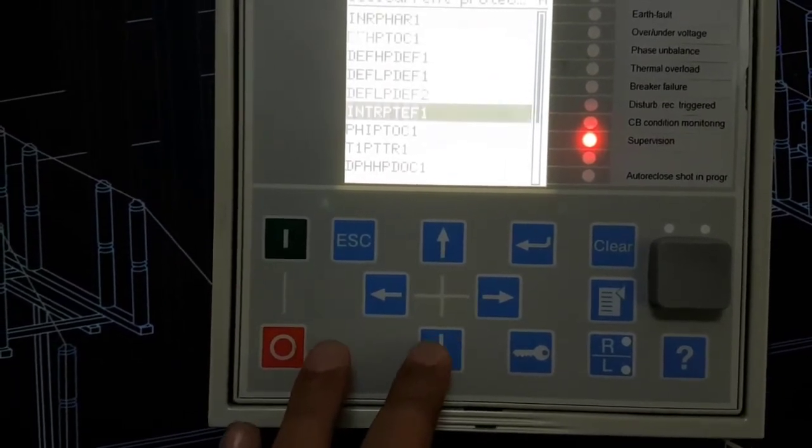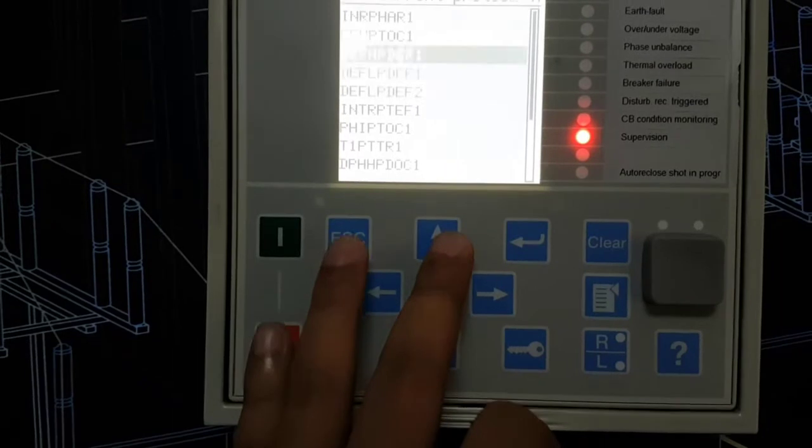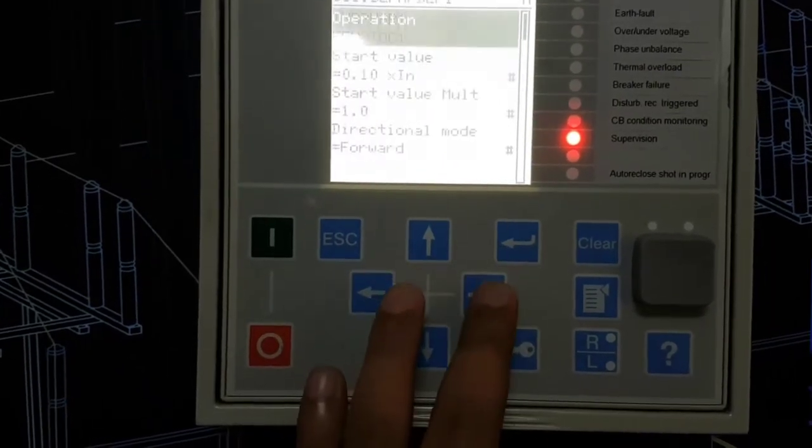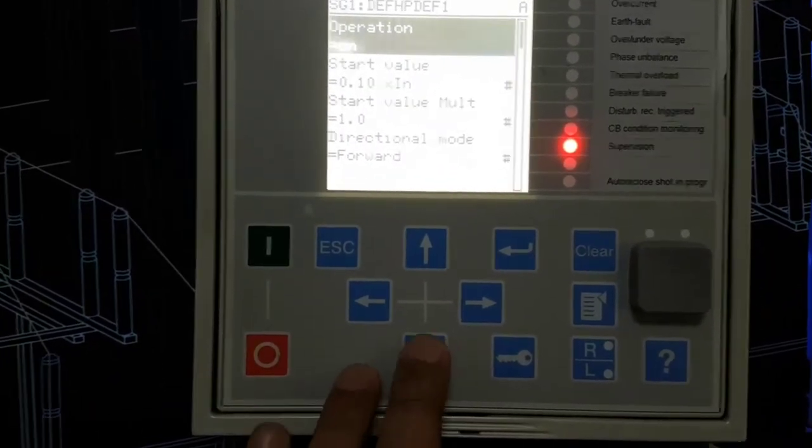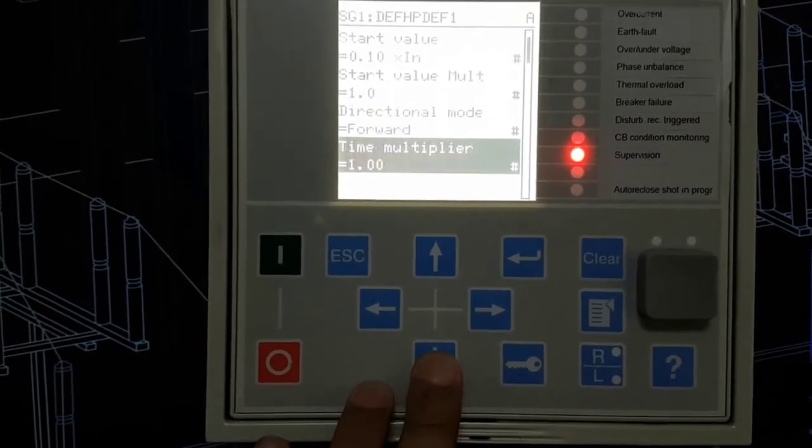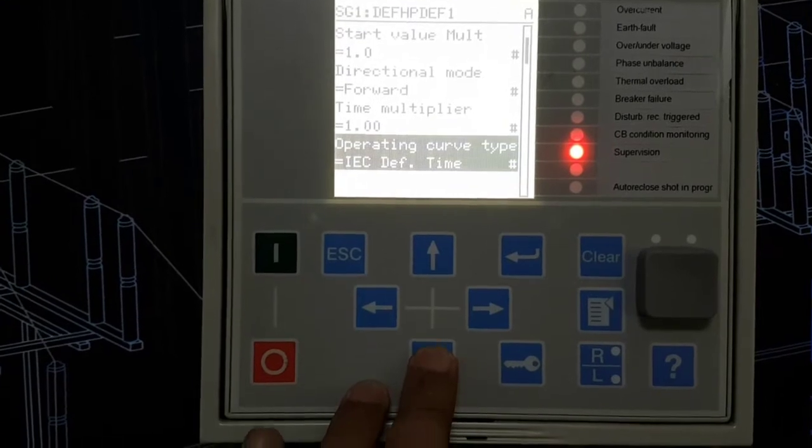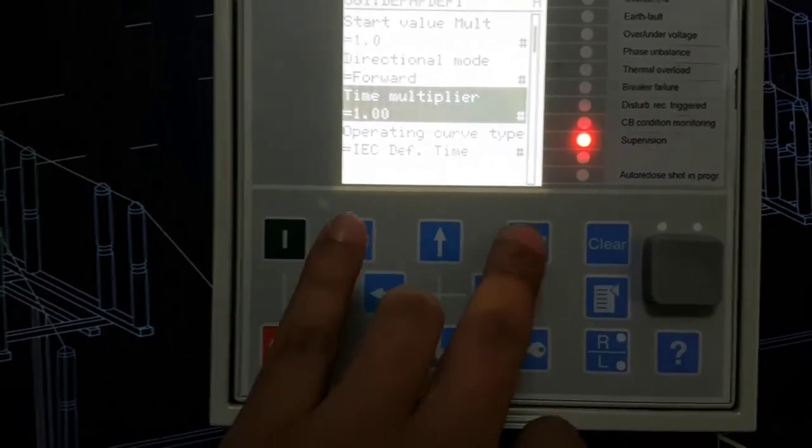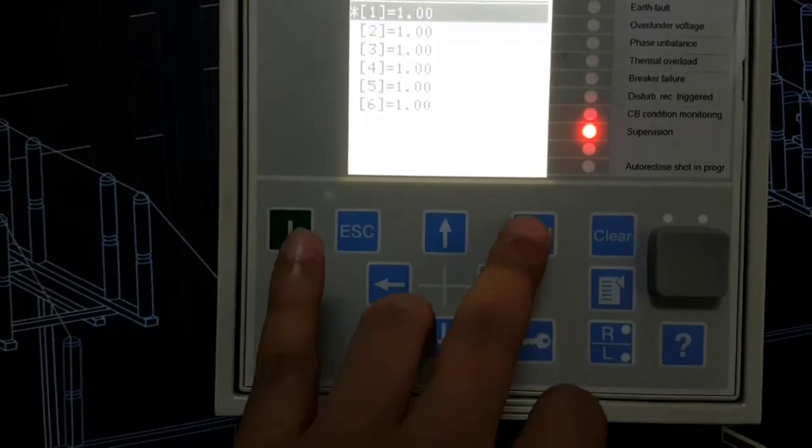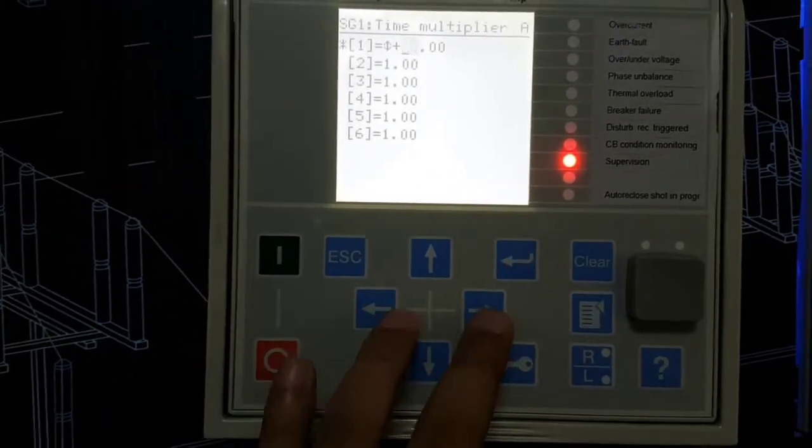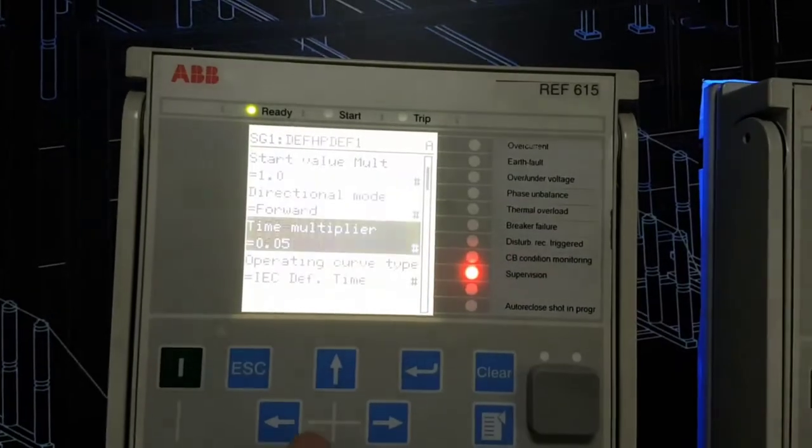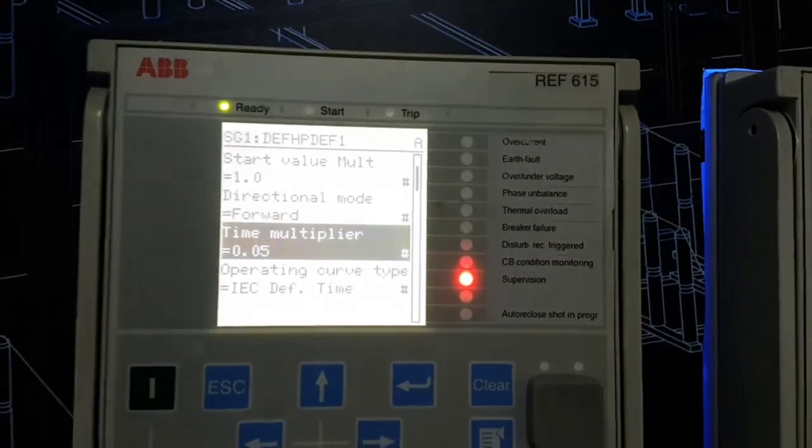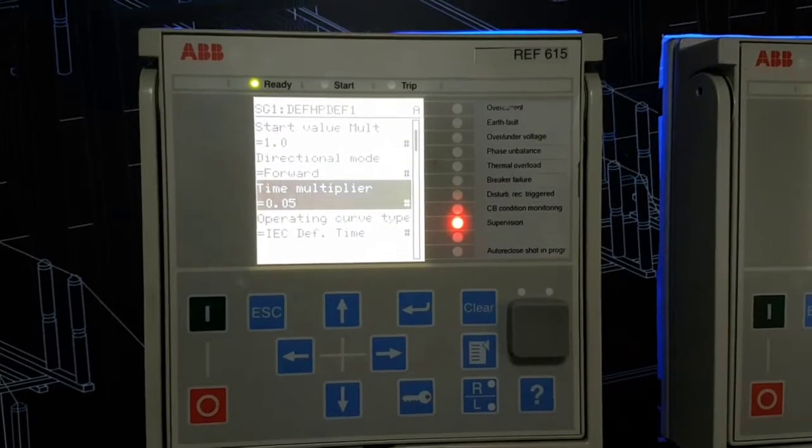Now directional earth fault setting. Here it is directional and there's forward time multiplier. It's set to one. You can change it as low as 0.05 and the operating curve type is here by default.